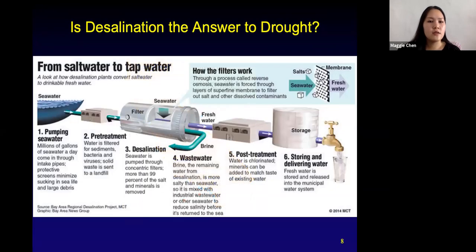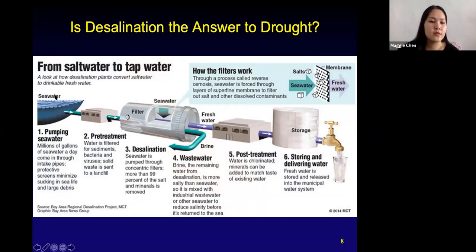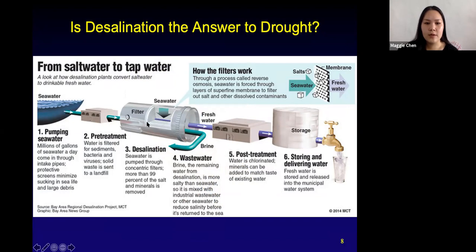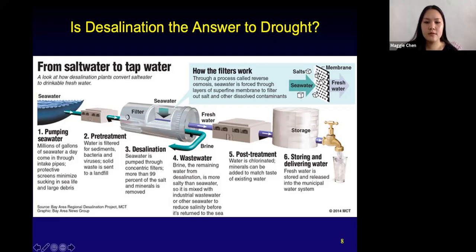Looking at a desalination plant: first, seawater goes through pretreatment, where bigger particles, bigger sediments, bacteria, and everything is taken out as much as possible and sent to a landfill. That water is then sent to the desalination step, where it's forced through several filters using the process of reverse osmosis, which removes almost all of the salts from the seawater. At the end, just like in the distillation process in lab, there is brine that comes out along with fresh water.